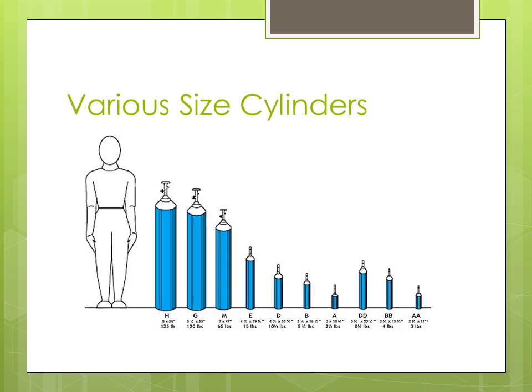You can have the empty cylinders in addition to that, but they have to be considered empty, and they have to be in a separate holding area that says empty. Now, are they truly always empty? Not necessarily, but that is sort of the line that you walk, and that gets us into lots and lots of trouble in lots of areas. The other thing about these cylinders, which is very critical to understand, is securing them. They have to be secure. They cannot be laying on their sides. They have to be properly secured, and we're going to look at a couple images on that in a minute.